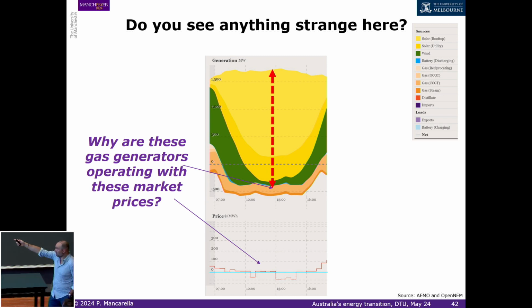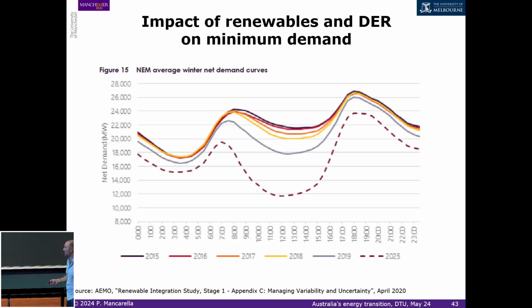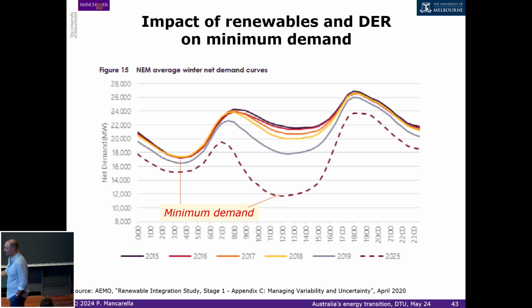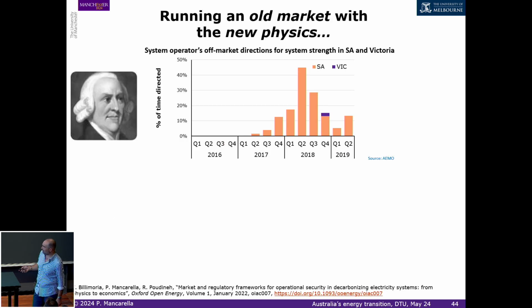So at the moment, if we do not have many options, the system operator asks all these turbines to run, to provide the services, even if the energy market says it should not do that. Unfortunately, this is happening because the minimum demand in many cases is now happening during the day and not during the night as it used to be. During the day, when there is all this rooftop PV in the grid, effectively the system operator doesn't know what is happening. In order to provide stability, you just say, well, I need to use my synchronous machines there to help me, because if there is a problem, it might cascade.